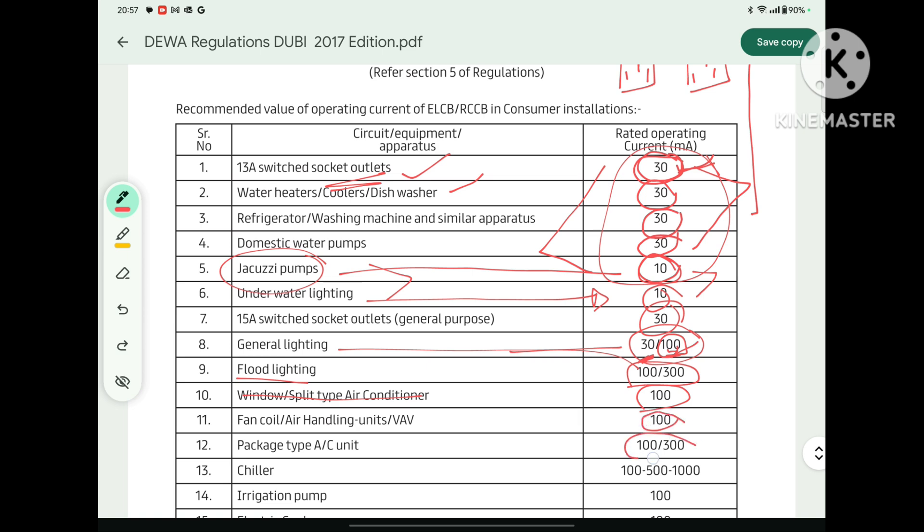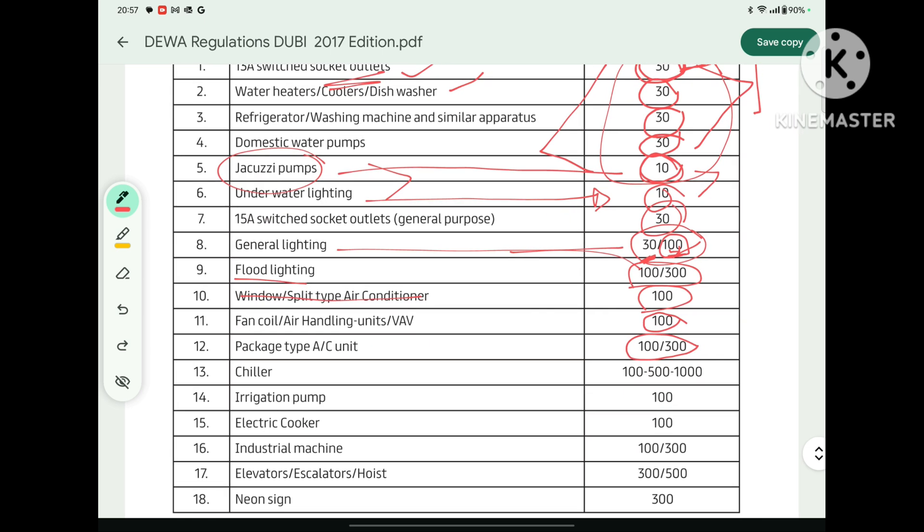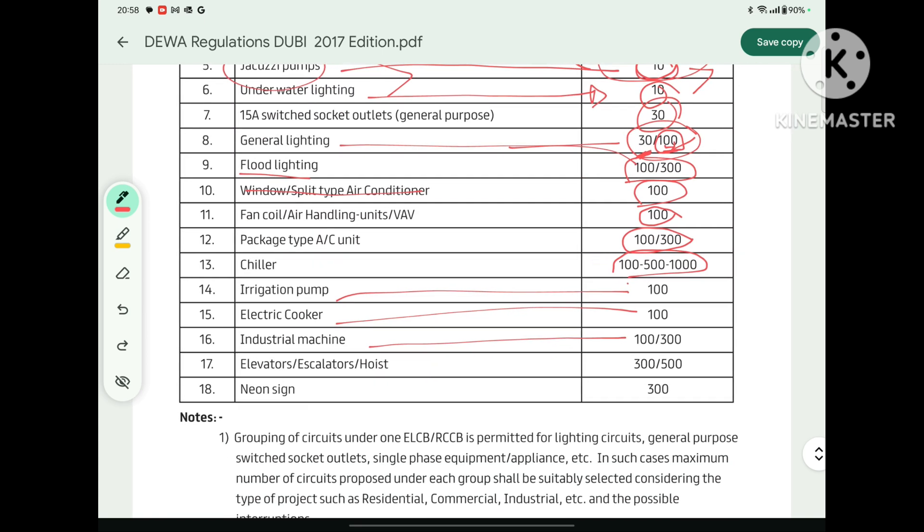For package units, the rating will be 100 mA or 300 mA. For chillers, it should be 100 mA, 500 mA, or 1000 mA. For irrigation pumps, it will be 100 mA. Electric cooker is 100 mA. Industrial machines are 100 mA or 300 mA.